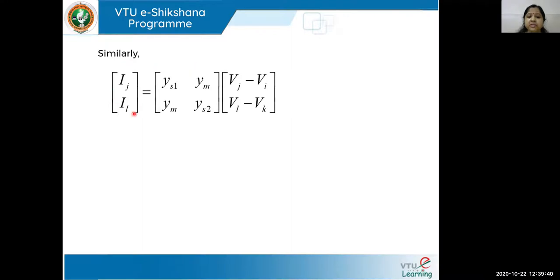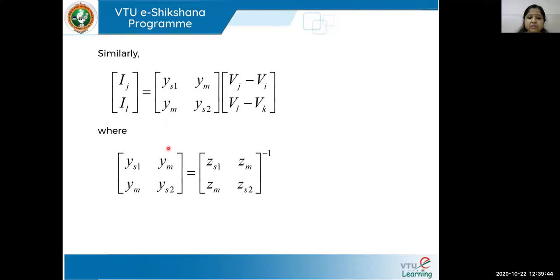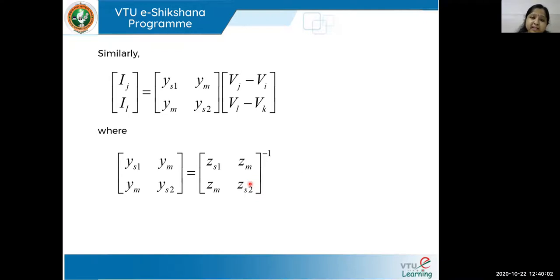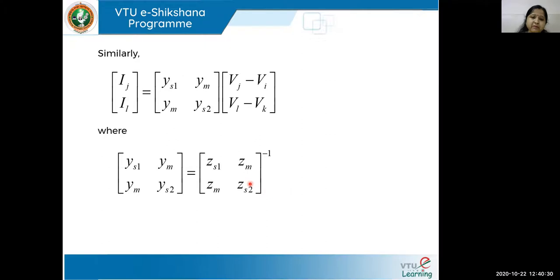Writing the equations back in admittance form: the inverse of the admittance gives the impedance. For a mutual coupling problem, first we take the Z primitive, then we take its inverse to get the Y primitive, and then we apply the singular transformation method formula: A-transpose multiplied by Y-primitive multiplied by A (the bus incidence matrix). Once we get the complete Y bus, we can take its inverse to get the Z bus.